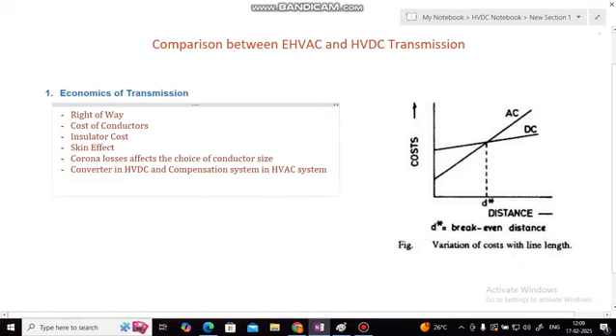And if we talk about reactive power compensation, then it is very necessary in HVAC system. For the reactive power compensation, it is required to set up a substation after every 60 to 70 kilometers. While in HVDC, there is no need to provide compensation after some distance. So power can be transmitted over long distance without any compensation. So in terms of reactive power compensation, HVDC system is better than HVAC.